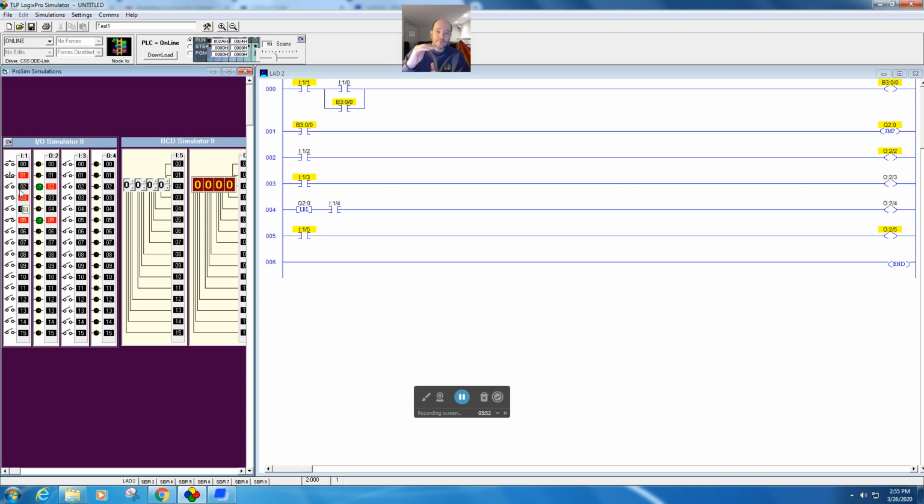So the hard part about using the jump to label instruction is that you have to make sure that everything is in the proper state before you decide to jump over things. There can also be some serious scan time issues with trying to jump into another jump fenced zone or jumping backwards, and that can cause some scan time issues, which can be really, really hard to overcome.